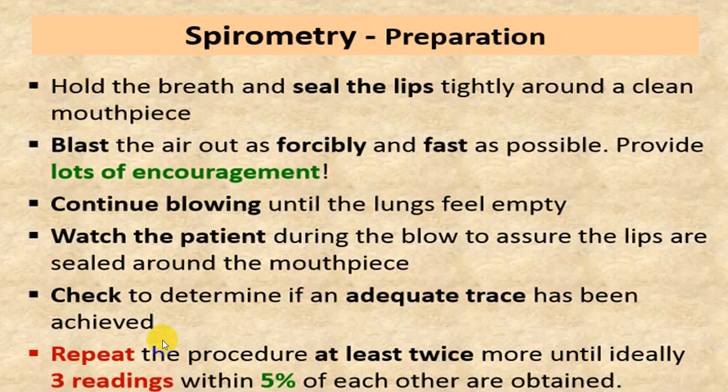And then you should have a minimum of 3 readings. Out of that, get the best 2 readings and then decide regarding which is the best. So repeat the procedure at least twice more until you get 3 good readings, which are obtained within 5% of each other.